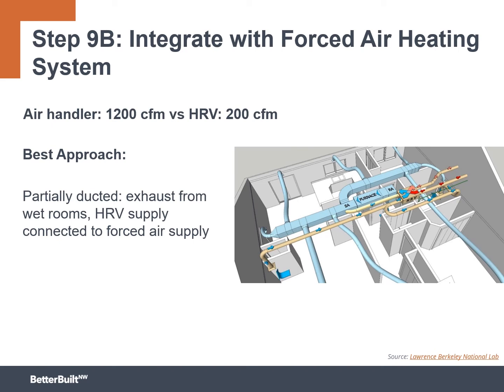The best approach for doing something like this is, first of all, let's be realistic about how much airflow is being moved. That central air handler running at full speed is likely moving anywhere from 1,000 to 1,600 cubic feet per minute, whereas an HRV might be moving anywhere from 50 to 250 CFM. Very different orders of magnitude. So because of that, we want to make sure that, let's say, 200 CFM of HRV air actually blends very well into that larger airstream.